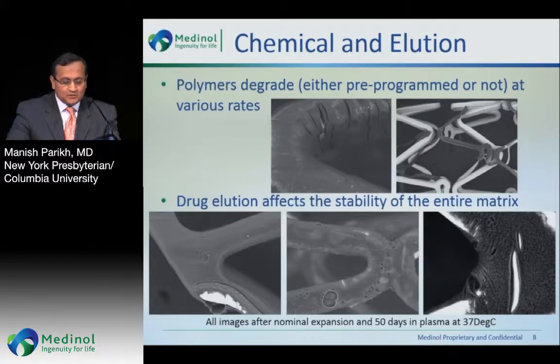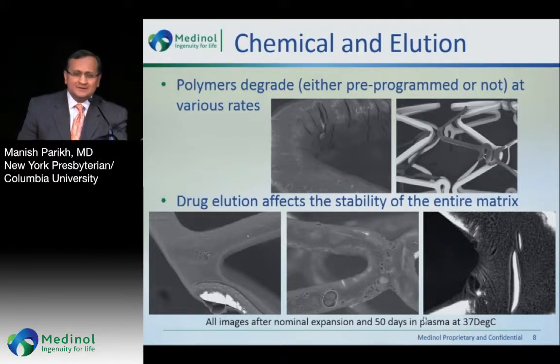The chemical and elution process also causes a tremendous amount of degradation. Some of it is pre-programmed, some is not. The drug elution actually affects the stability of the entire matrix. Here is the Promus Premier again. This is the Resolute with pocketing and inhomogeneous mixing. And this is a Synergy platform after expansion — look at the immense amount of peeling, cracking, and craters in the middle of this Resolute stent, and chipping with exposure of the metal underneath.